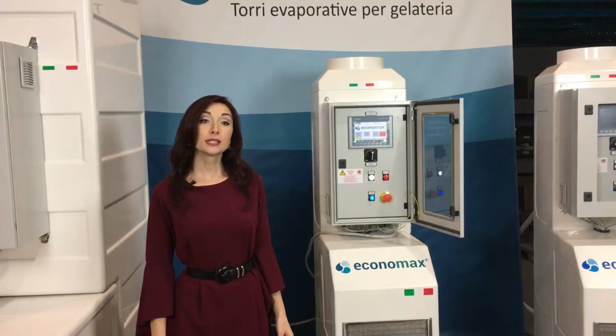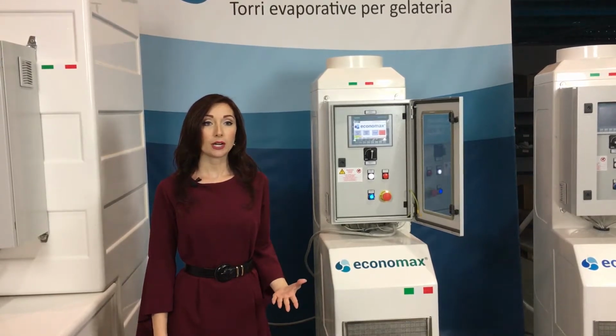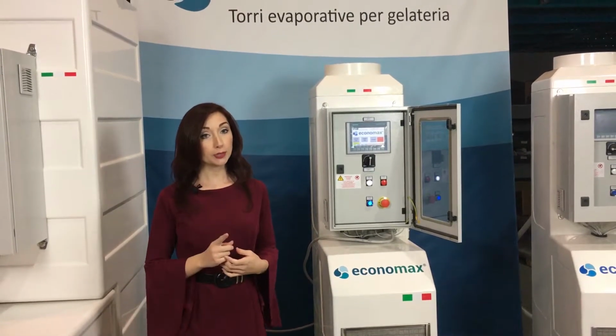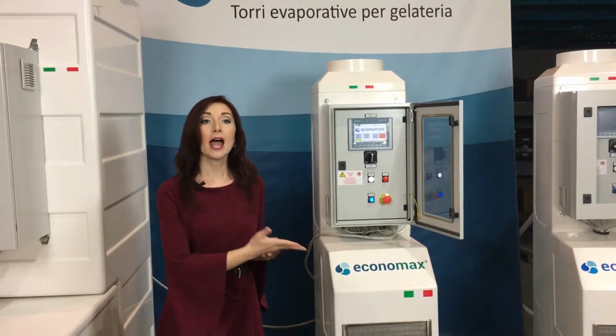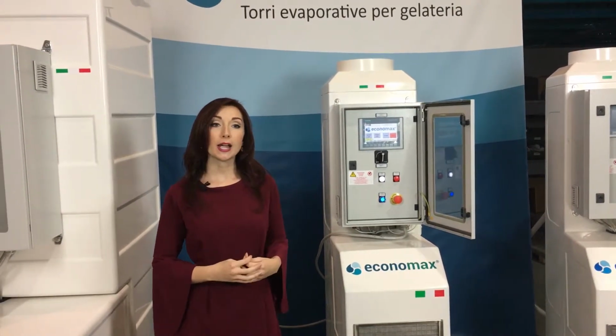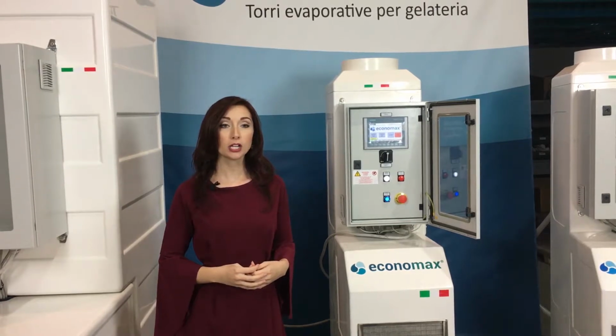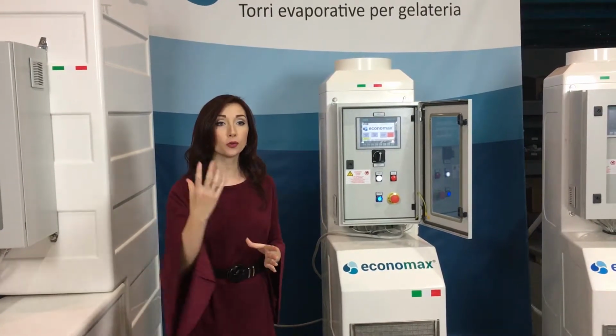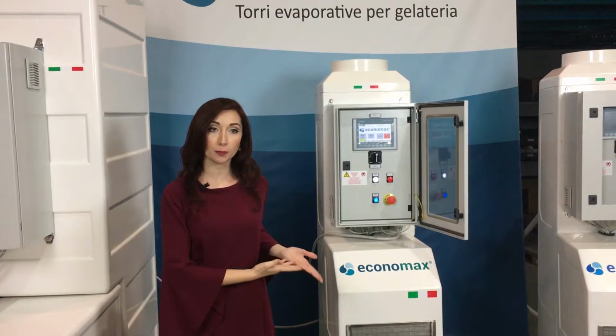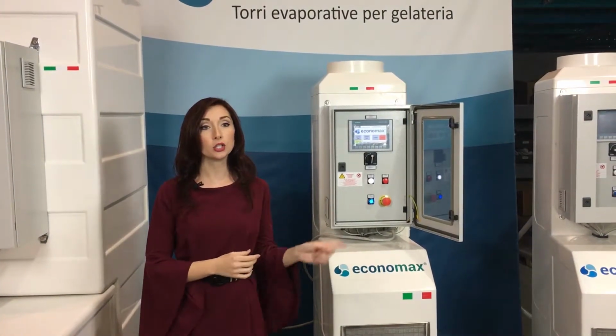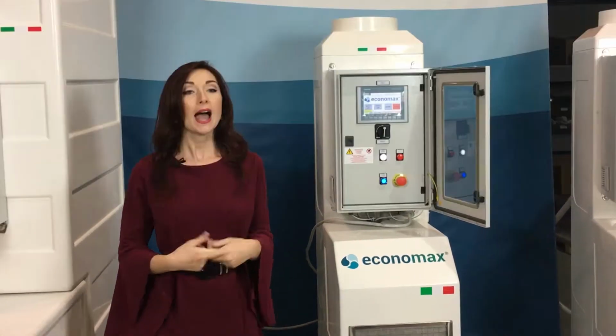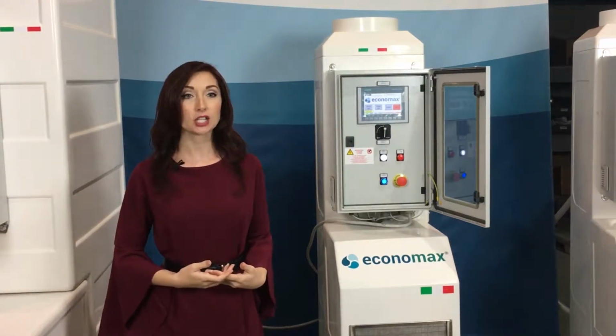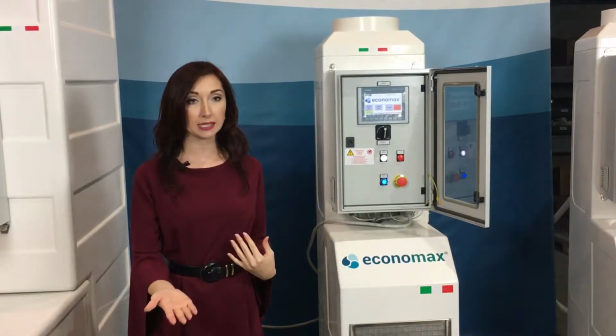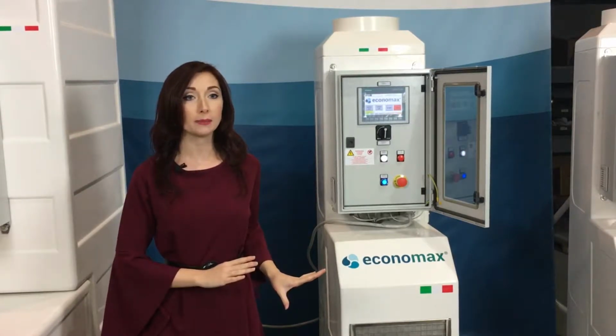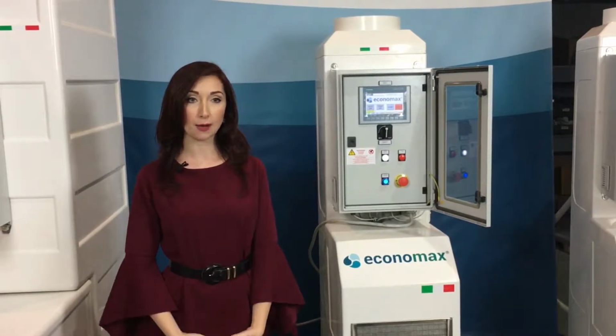Installation. Let's quickly look at the installation. To recycle water, the ECONOMAX tower requires the simple creation of a loop system between the tower itself and the workroom machines. This way, the circulation pump can send water to the whole system, making it go through the heat exchanging material with which the tower is equipped and sending the newly cooled water back to the machines. After securing all the hydraulic connections from the main system to the machines, the input tube from the main water supply is connected to the tank of the tower.